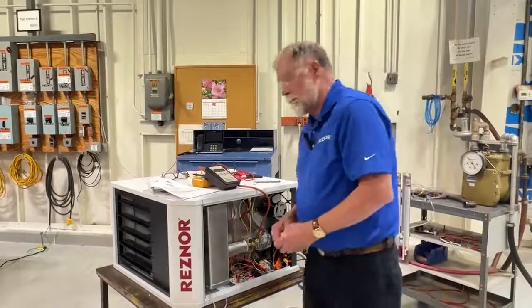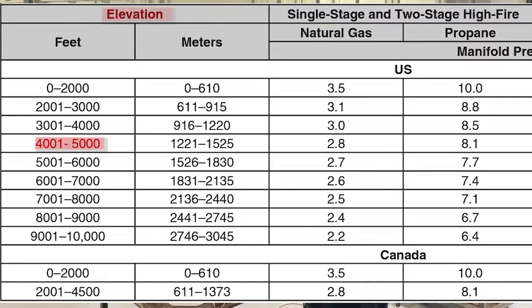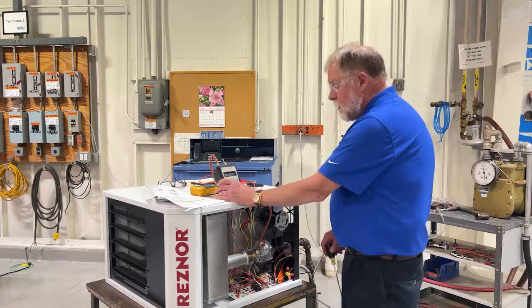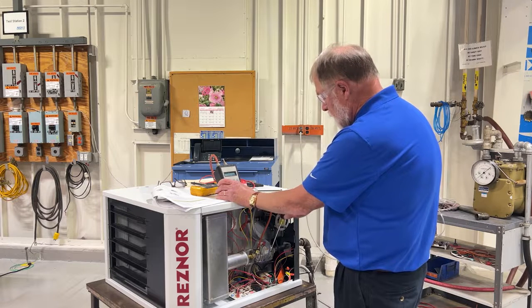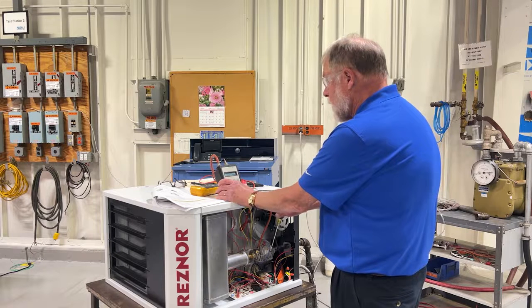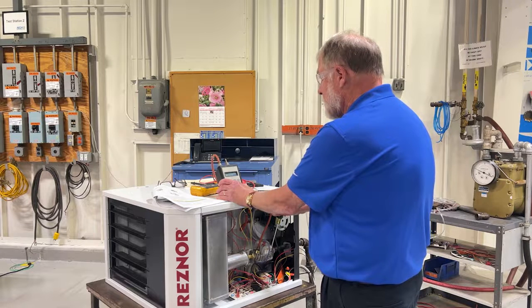We're going to set this heater up today for 4,000 feet. The required manifold pressure for 4,000 feet is based on the information in the installation manual. We have ignition, and right now this unit is running at approximately 3.7 inches of manifold pressure. We're going to decrease that pressure very slightly to get it to 2.8 inches, which is the required maximum manifold pressure for an altitude of 4,000 to 5,000 feet.